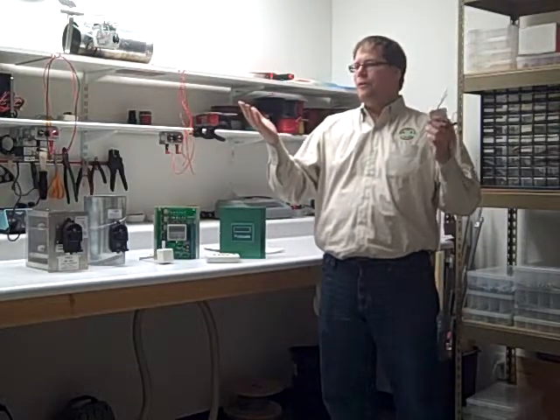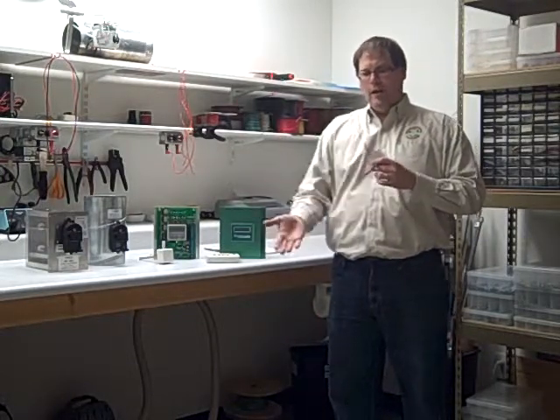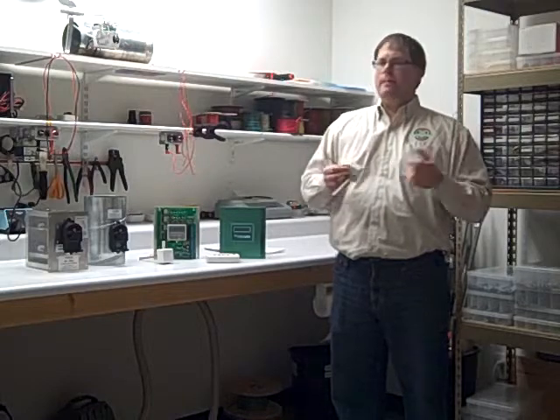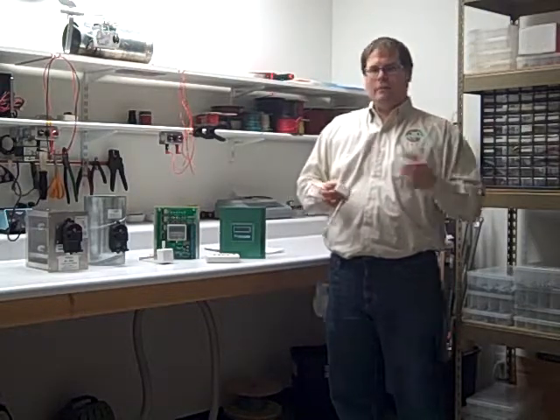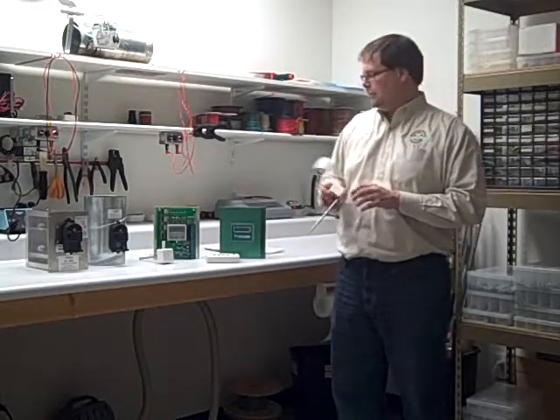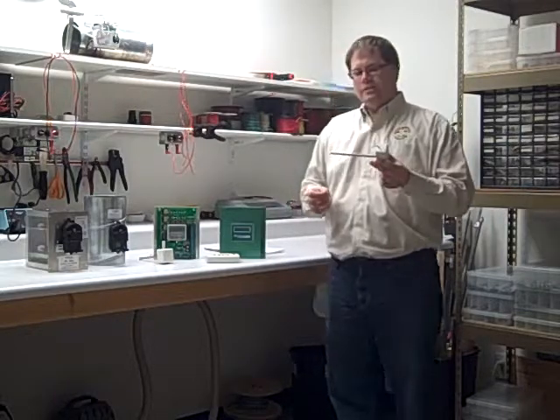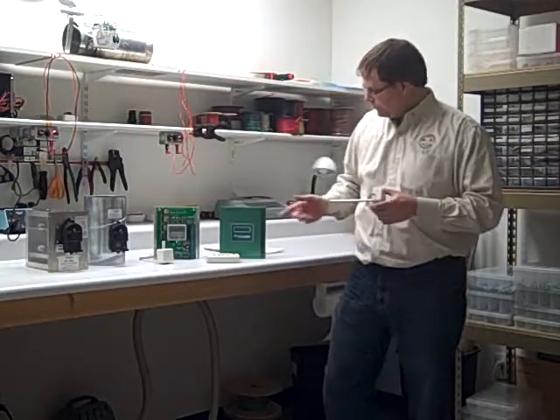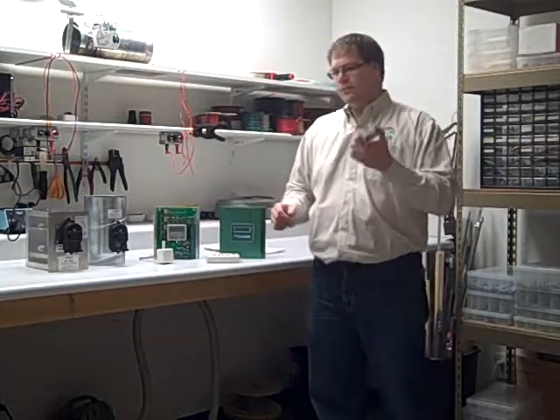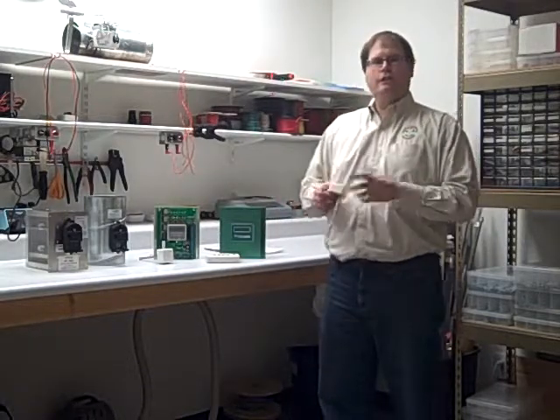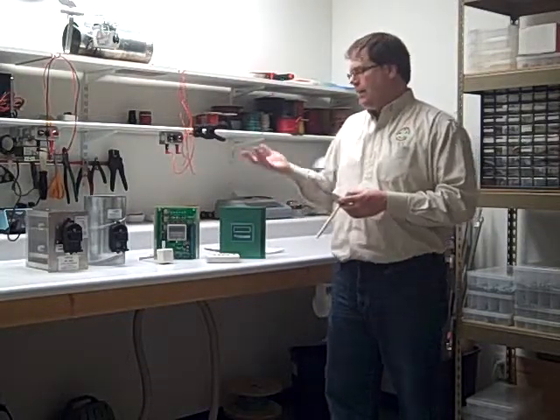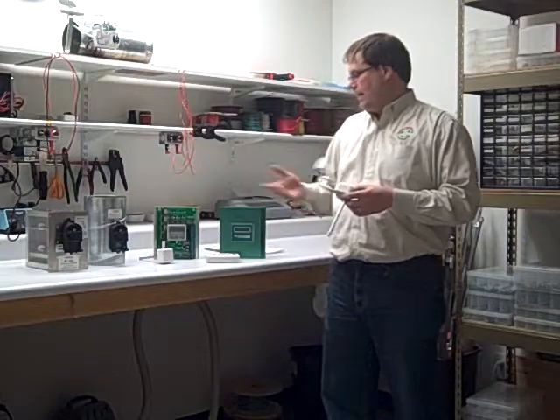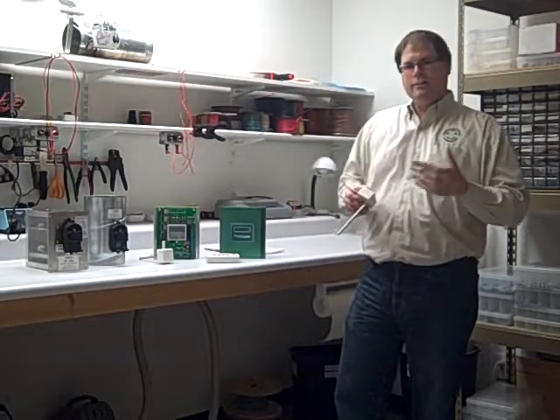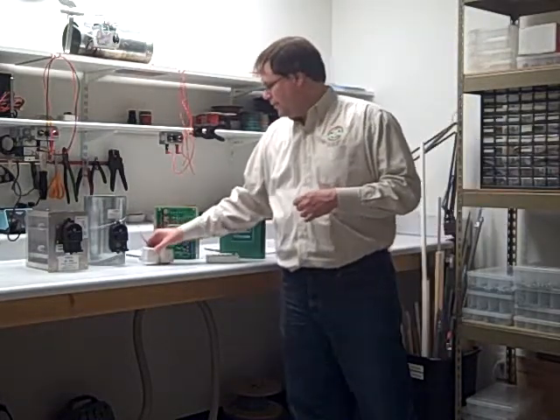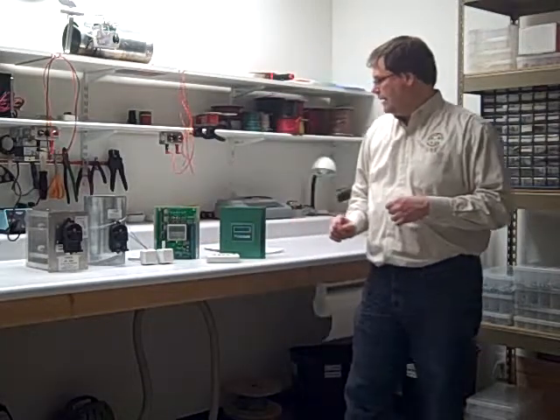It's a high and low limit. If we go below or above, we would bring on the equipment, make sure pipes don't freeze or we're not going to get the house up to 100 degrees. So both the sensors come with it and can wire in to the return air sensor or the discharge air sensor. And then also if you're doing dual fuel, you can get an outdoor thermostat or an outdoor sensor to do your dual fuel balance points. So there would be a third sensor if you're doing that.